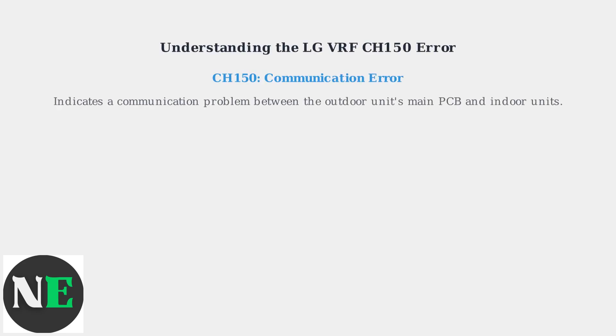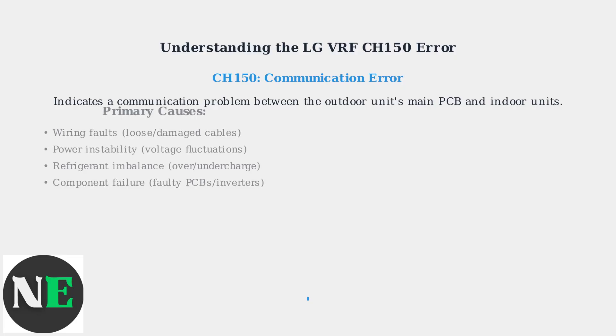The LG VRF CH150 error code indicates a communication problem between the outdoor unit's main PCB and the indoor units. Primary causes include wiring faults like loose or damaged cables, power instability from voltage fluctuations, refrigerant imbalance from over or undercharge, and component failure in PCBs or inverters.